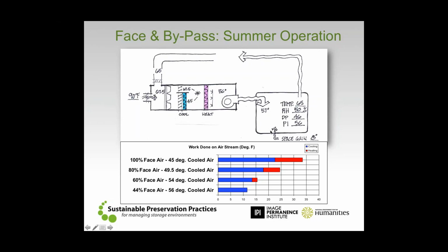But here's that blend, right? And notice that this is keeping the same set point condition out in the space, 65 degrees at 50% relative humidity. If we send 100% of the air over that cooling coil and cool it all down to 45 degrees, then here's the amount of work we have to do. There's our cooling energy, and here's the amount of reheat in order to achieve that condition in the space.